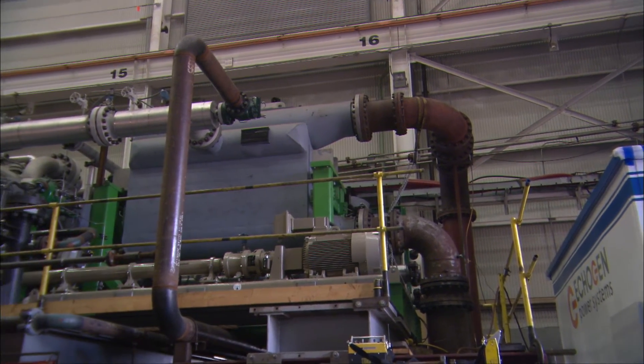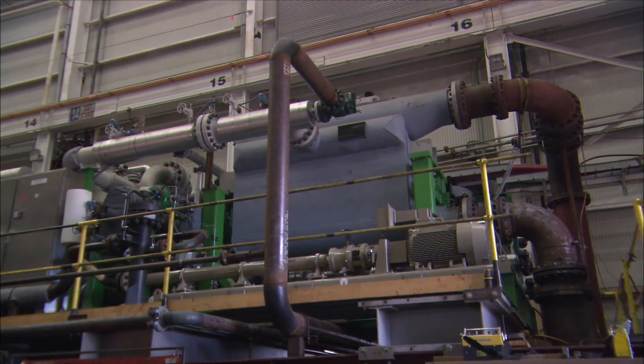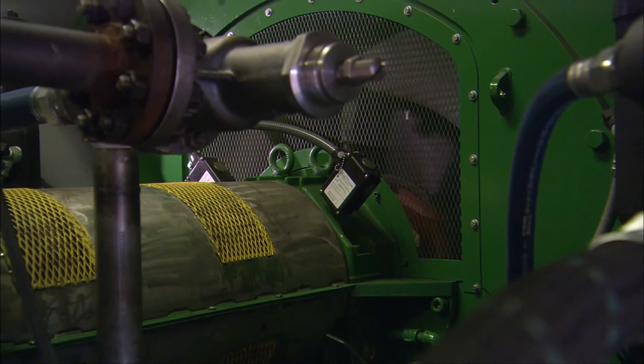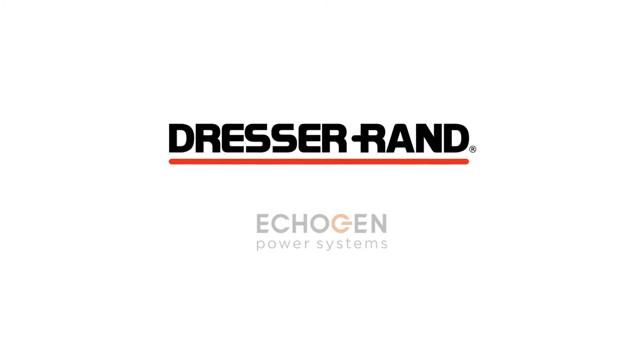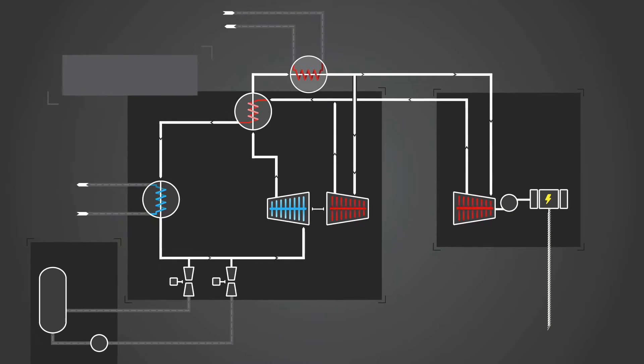We basically take heat that is otherwise unused in a process — whether it's from the exhaust of a gas turbine or from an industrial source — and use supercritical CO2 as the working fluid in a closed-loop cycle that generates electrical power. Dresser-Rand and Echogen have partnered to develop the EPS-100, an innovative new technology that converts on-site waste heat into electricity using supercritical CO2.